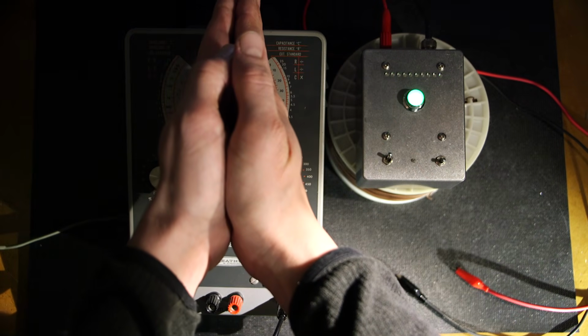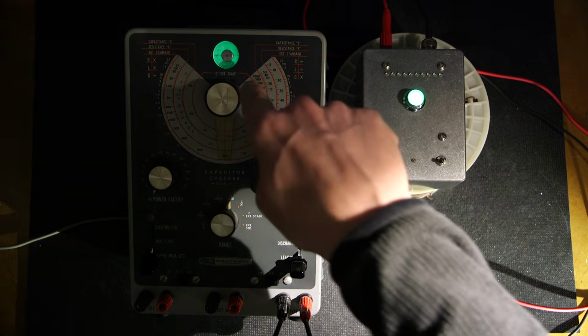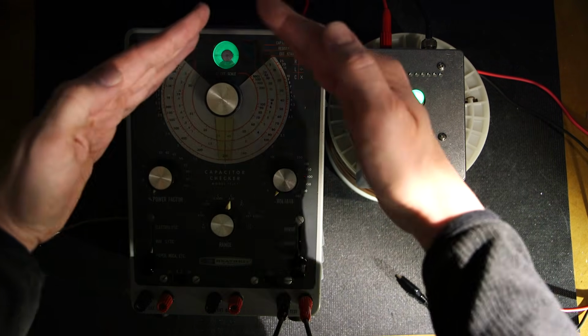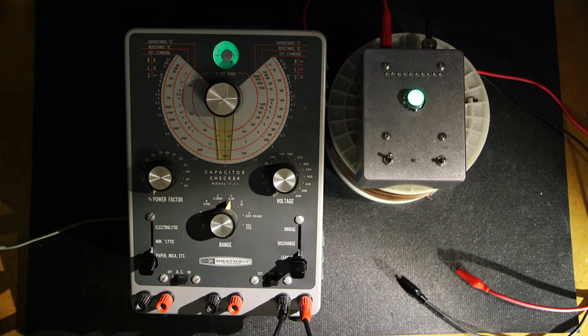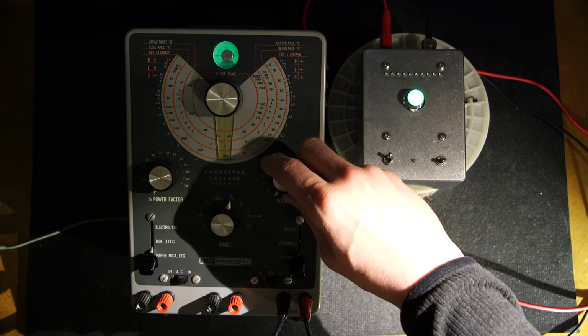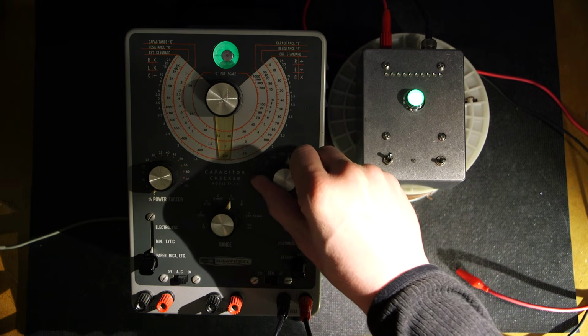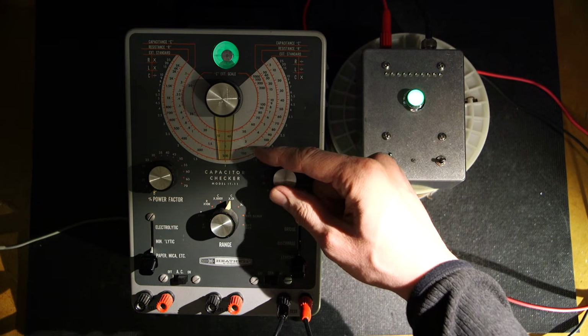So for leakage, I'll just advance this fast. If the eye closes, meaning the shadow angle changes and stays closed, it's a faulty capacitor. It can close briefly as it's charging, but if it returns to its open position, that means the capacitor is okay. When you see it closing like that, it's just charging the cap.